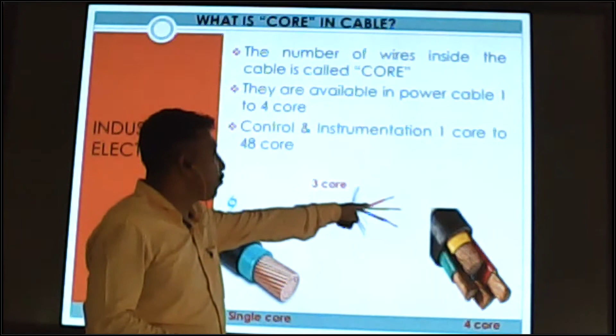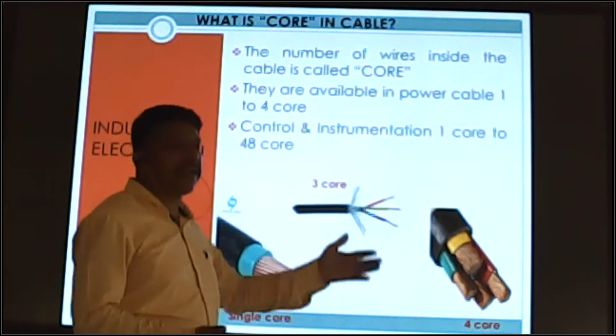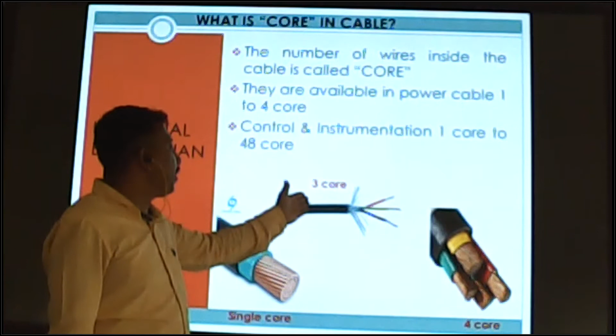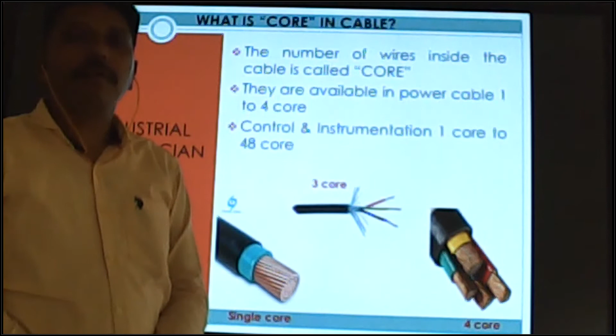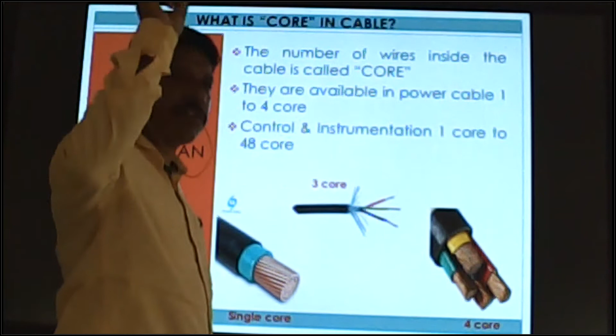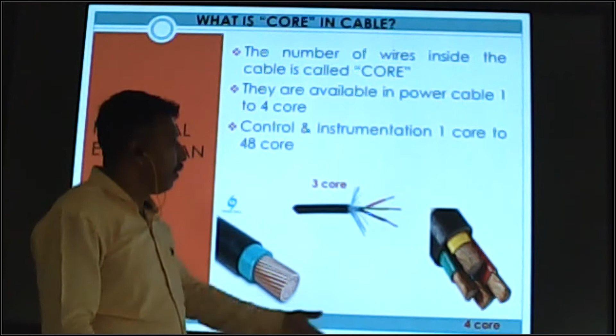3 core. There is a core color code also. We can check there. Yellow-green is used for earthing, red is used for phase, and black is used for neutral. This very simple 3 core we can use in single-phase power areas: single-phase DB, single-phase equipment, single-phase devices. We can use these types of cable there.